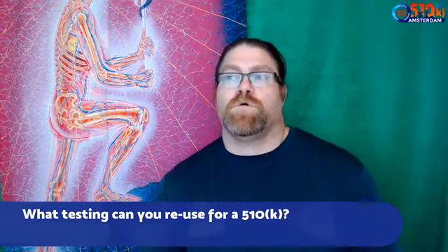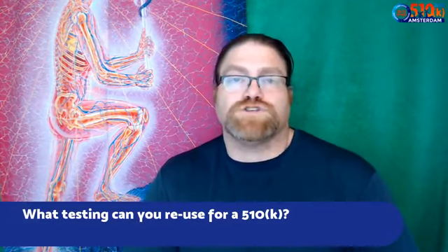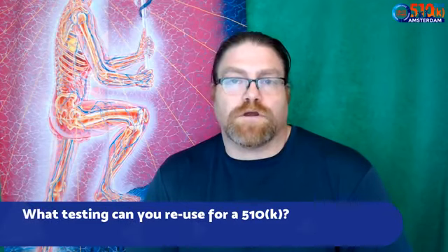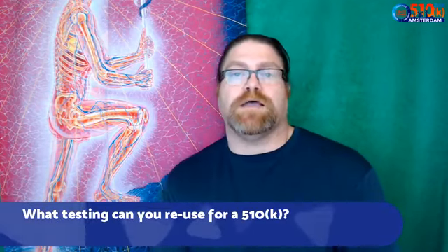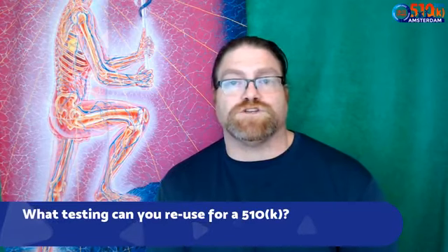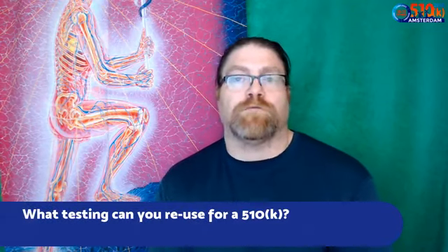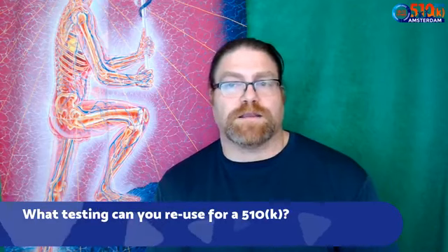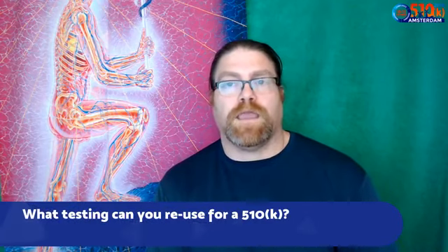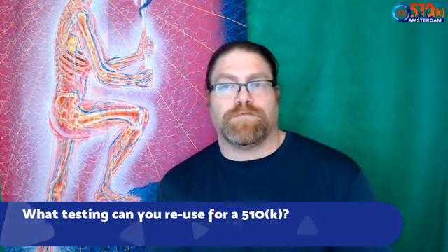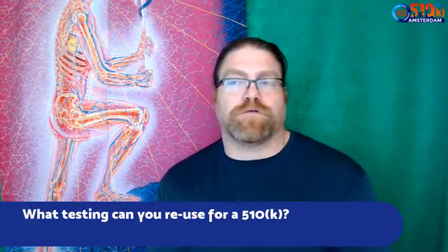So another question, what testing can you reuse for your 510K? In theory, almost all of your testing should be reusable for the FDA, but there are differences between the US and Europe. For instance, the US currently has electrical safety testing edition 3.1 that they're recognizing, whereas the Europeans are still recognizing version 2. That changes in the near future. For EMC testing, the FDA recognizes version 3, and for home use products, version 4, whereas the Europeans are still on 3, and they won't require 4 until January 1st.